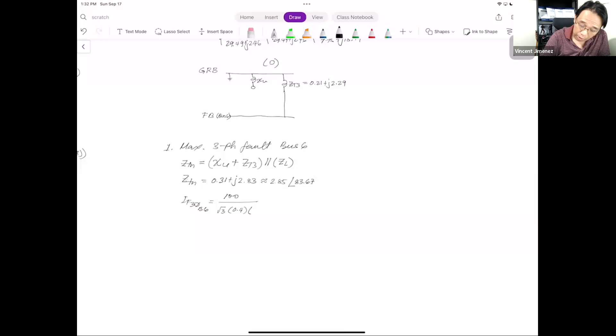Now we can compute the three-phase fault at bus 6, which is equal to 100 MVA over square root of 3 times the line voltage at bus 6, which is 400 volts, so 0.4 kV, and the per unit impedance magnitude of 2.85. This is equal to 50.6 kA. This is your maximum fault at bus 6. Let's call this the bus 6 calculation.